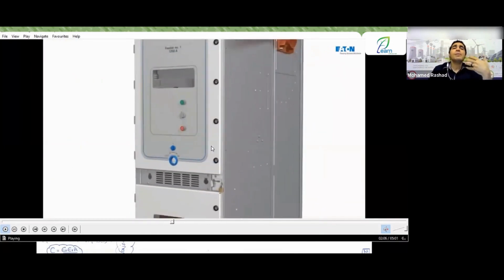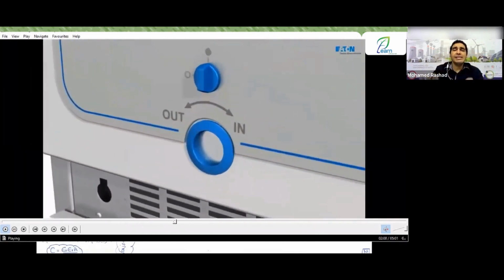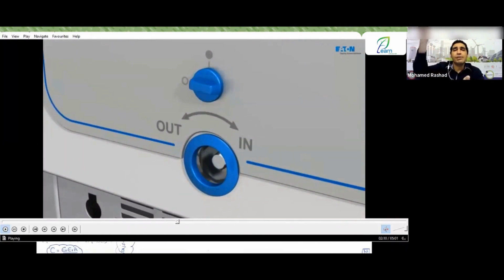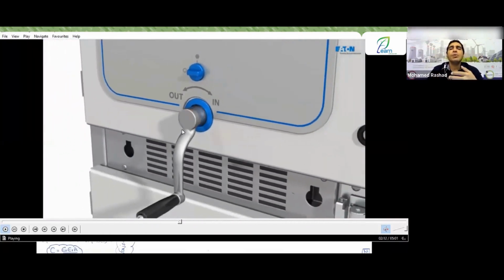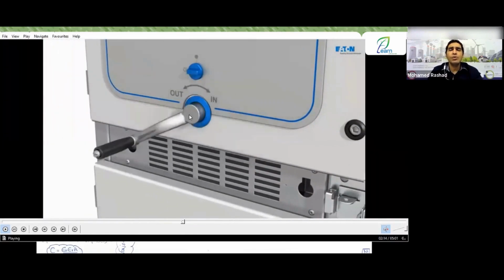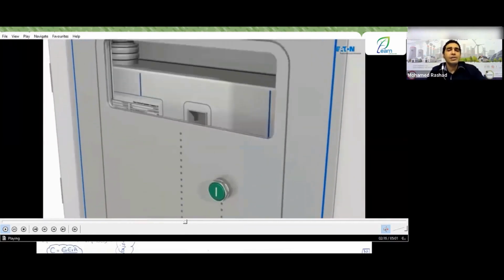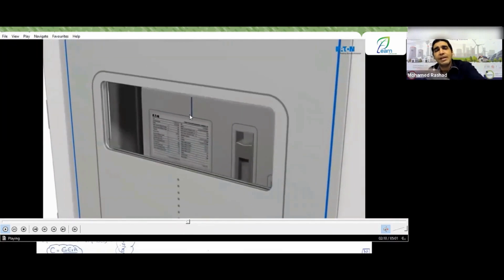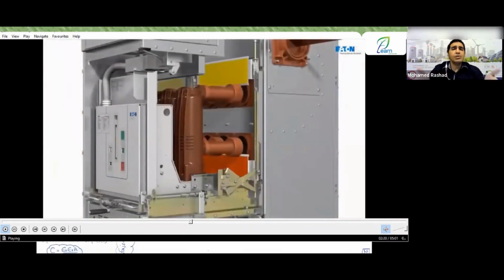If you want to insert the breaker, rack in, to start connecting electricity to a bus bar or draw electricity from a bus bar to deliver it to a load, you have something called the insertion hole. You start by inserting a handle into it and begin to turn it, starting to insert the air circuit breaker like a drawer, just like you would insert a desk drawer.